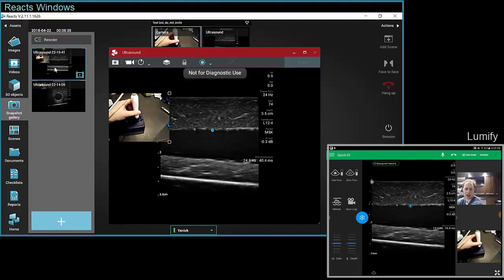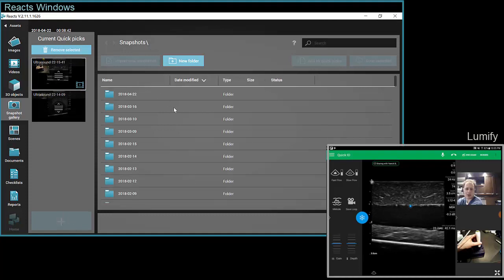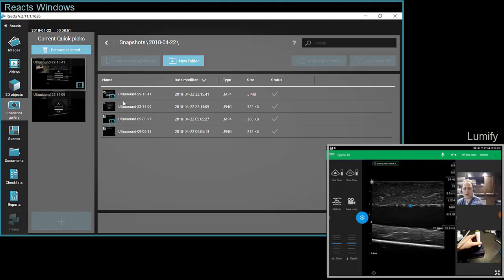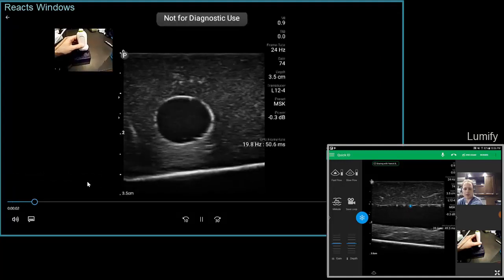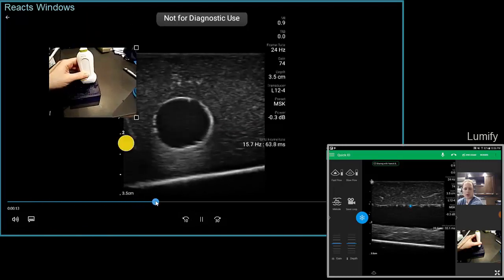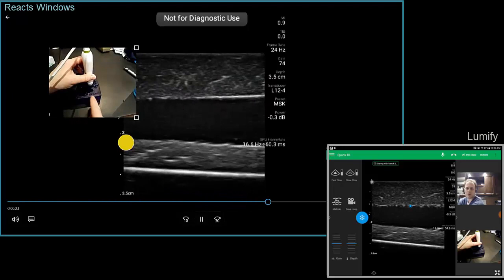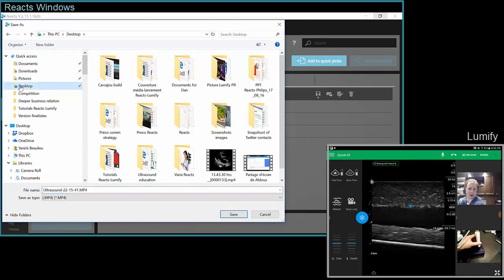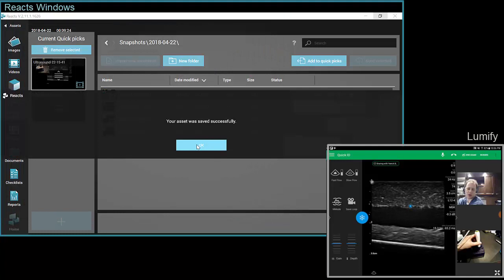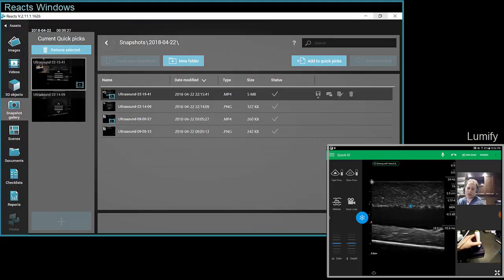The clip goes straight into the Reacts library. If you hit the big blue button it brings you to your Reacts snapshot library, where a folder is automatically created when you record something. Click on that folder to see all the images and videos you took during the session. Double-click on a video to open it right away and view the exact video you just recorded — it's an MP4. If you'd like to use that video in a PowerPoint presentation, go to your library, click the little disk to save locally, change the name, save, and it's done. You can also send it by email to someone who doesn't even have the Reacts application.